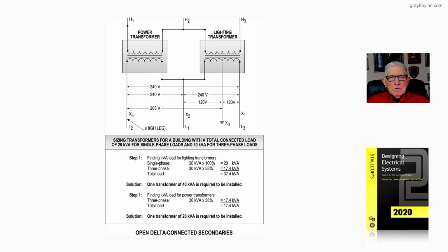So the solution is selecting an Acme transformer, which we did, is a 40 kVA. That's the next size above 37.4. So that's the solution for sizing the one transformer that we're looking at there. Now, the next step, we'd have a kVA load for the power transformer. And if you look at three phase, then it would be 30 kVA times 58%, 17.4, and that's what you would figure is the three phase load. 17.4, you'd come up with a 20 kVA.